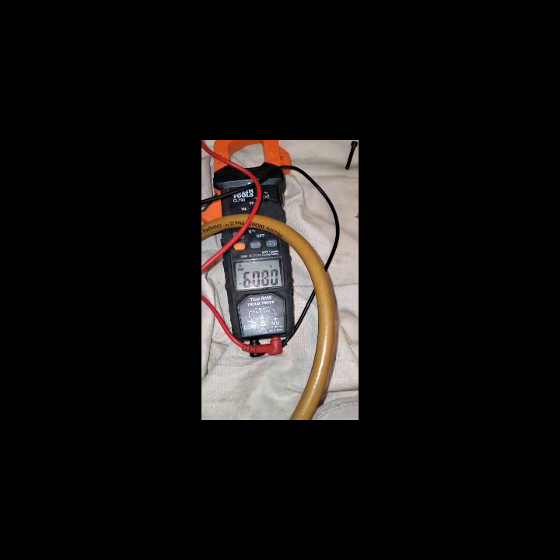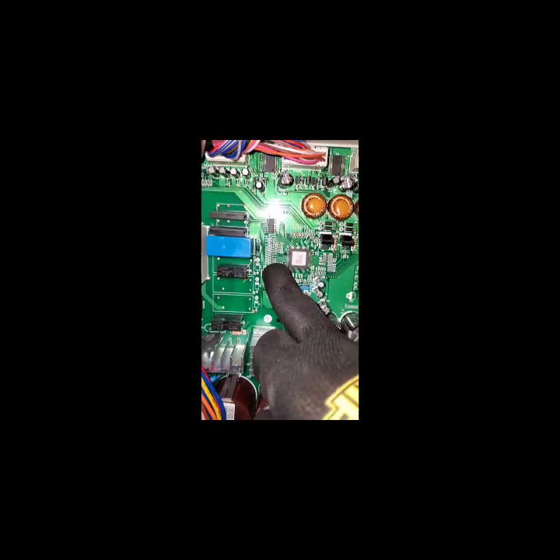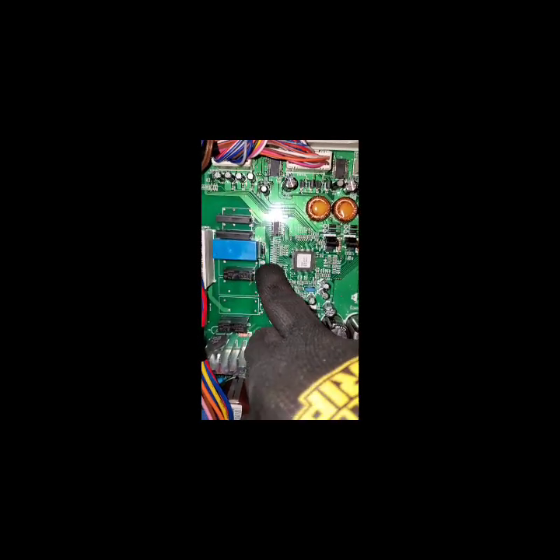So I plug the unit back in. I'm waiting for the condenser fan to kick on. Look at these dirty condenser coils, make sure you clean those up. But I'm waiting for my condenser fan. My condenser fan kicked on. Now I'm gonna wait the 30 seconds. While I'm waiting the 30 seconds I'm just monitoring my volts AC. Due to the fact that it's linear, these LGs like to start low and then they start gaining momentum. As you see here it's going from 36 to 39.